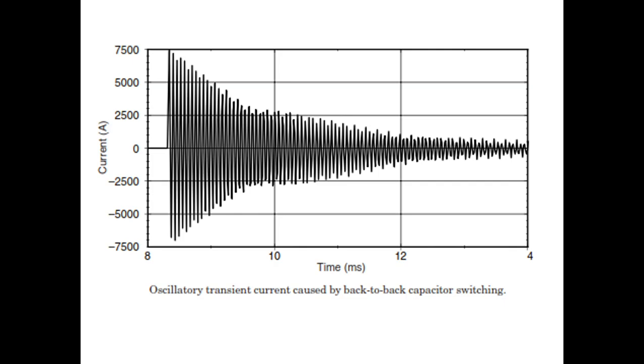In this diagram you will see how the transients appear. This is an oscillatory transient current caused by back-to-back capacitor switching. Capacitor switching means charging and discharging of the capacitor. In that case you get a waveform like this, which is called an oscillatory transient. The graph shows time in milliseconds, so the transients last for a few milliseconds, and you can see on the diagram how the current is disturbed.